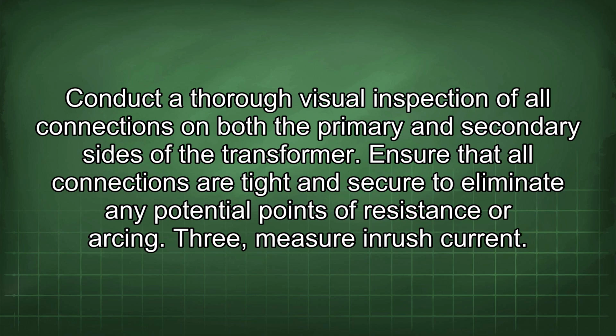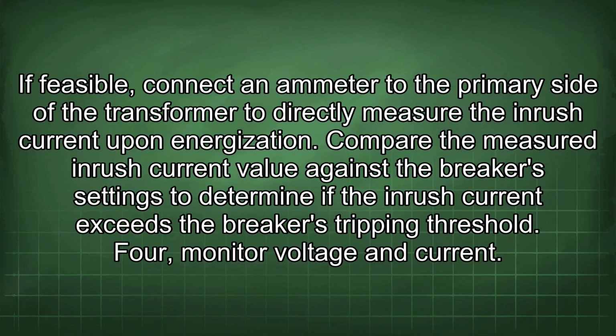3. Measure inrush current. If feasible, connect an ammeter to the primary side of the transformer to directly measure the inrush current upon energization. Compare the measured inrush current value against the breaker settings to determine if the inrush current exceeds the breaker's tripping threshold.